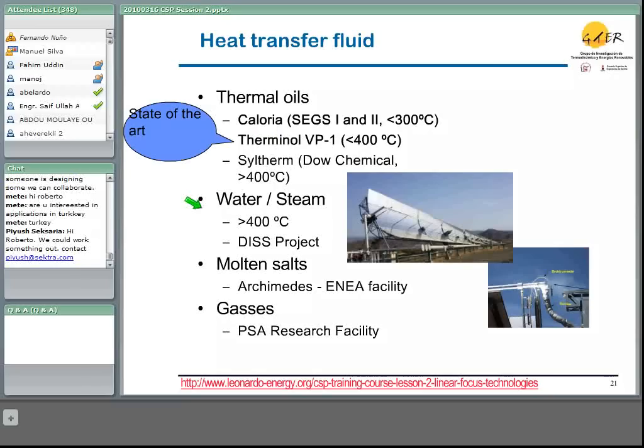It's the direct generation of steam in the solar field. With water you don't have the temperature limit, you can operate at temperatures higher than 400 degrees C. That's an advantage from the point of view of the power block, the steam turbine. You can operate at higher temperature, you can achieve higher efficiencies.